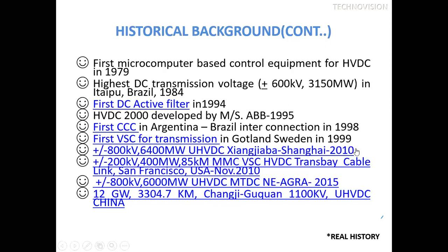But India later developed, as we already talked about, multi-terminal DC, that is plus minus 800 kV, 6,000 megawatt capacity, the Northeast Agra project. And before that, there was one voltage source converter based HVDC developed in San Francisco, USA. It is plus minus 200 kV, 400 megawatt, 85 kilometer with the MMC, modular multi-level converters. This is a voltage source converter based technology, but it is modular multi-level converter based.